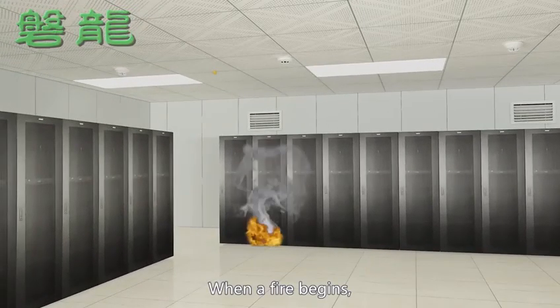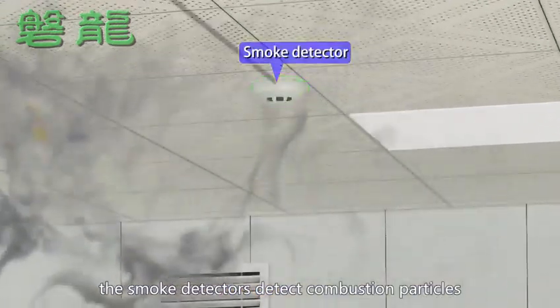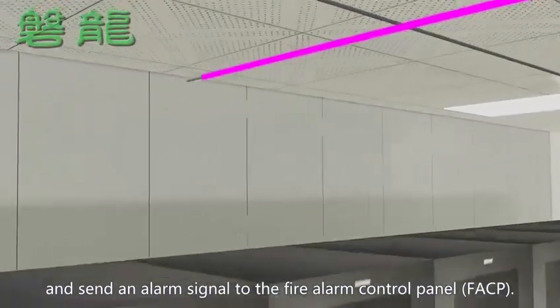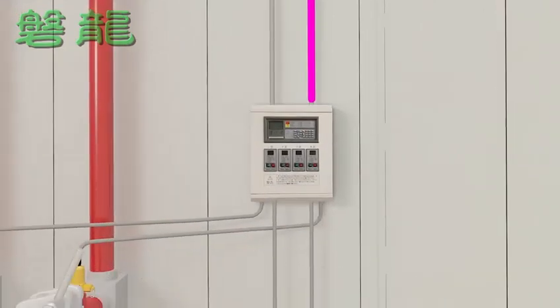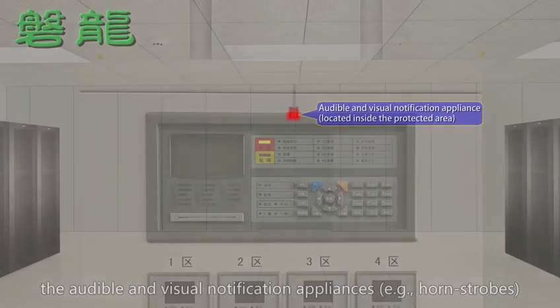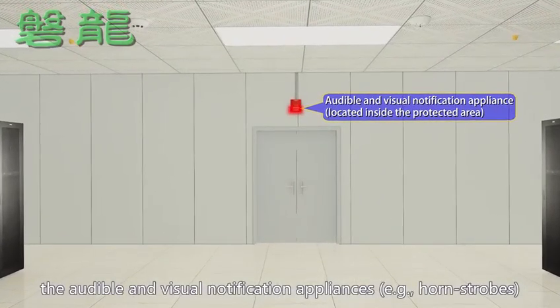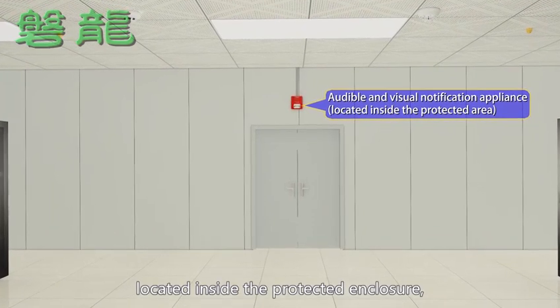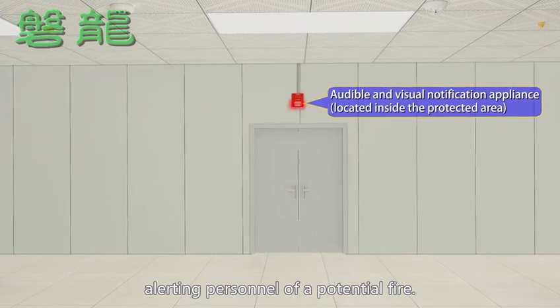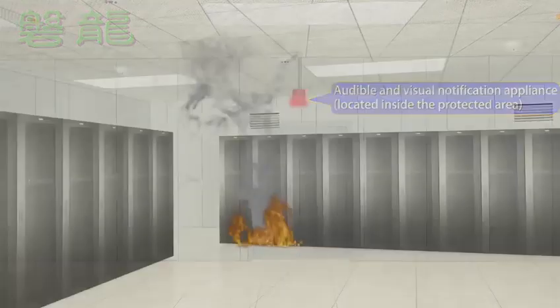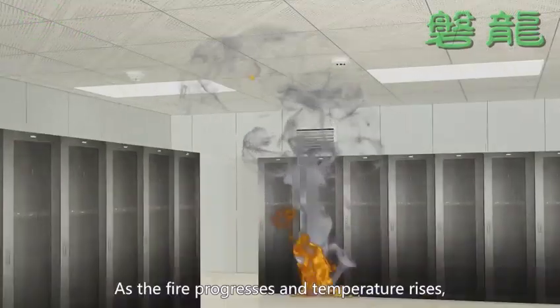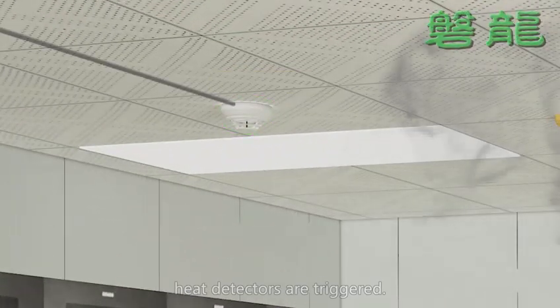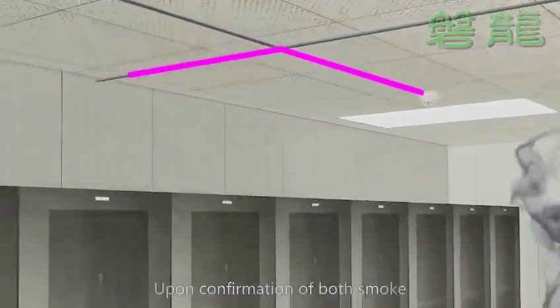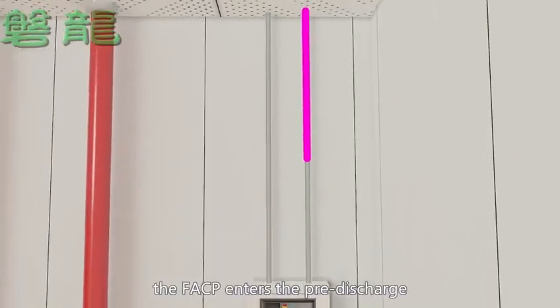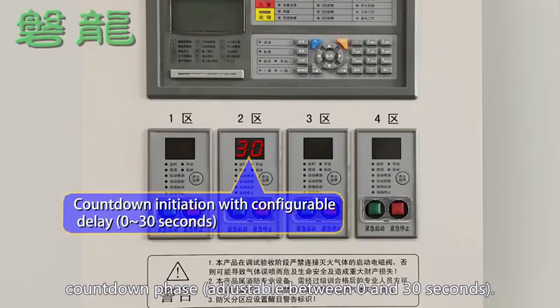When a fire begins, the smoke detectors detect combustion particles and send an alarm signal to the fire alarm control panel. The FACP activates the audible and visual notification appliances located inside the protected enclosure, alerting personnel of a potential fire. As the fire progresses and temperature rises, heat detectors are triggered. Upon confirmation of both smoke and heat signals, the FACP enters the pre-discharge countdown phase.